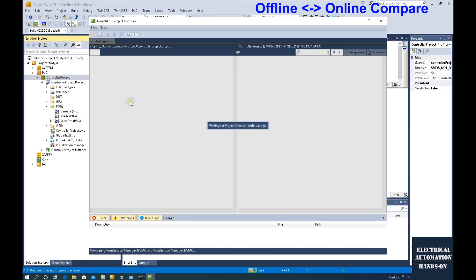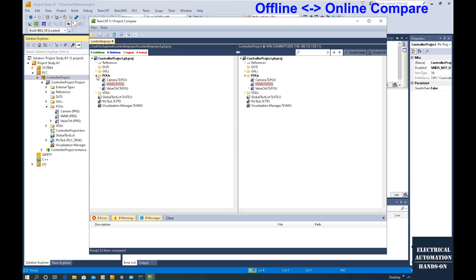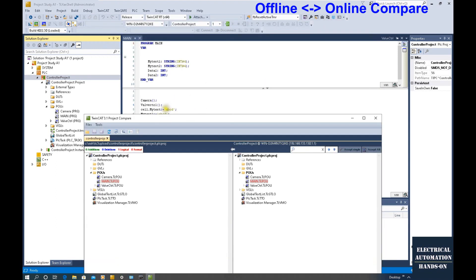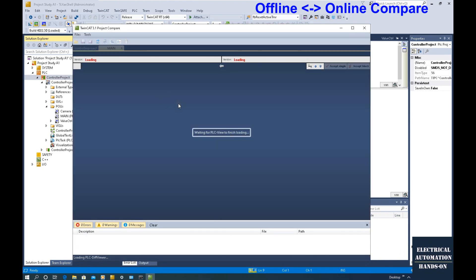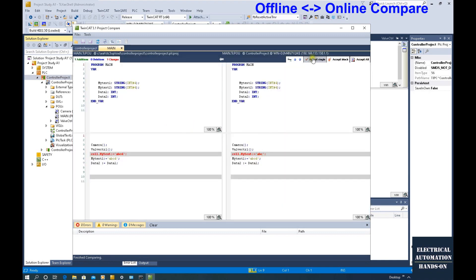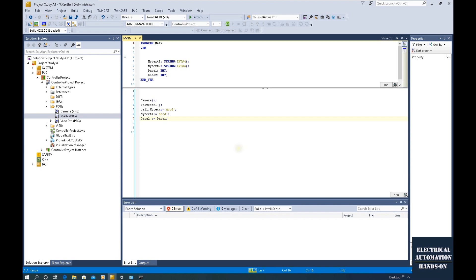The online PLC shows there the change. This way we can quickly find out where we changed — from offline comparing online. And another way we can compare offline with another offline project. For example, find the TwinCat config mode icon, right-click, go to Tools, and here is 'TwinCat Project Compare'. This is the source, and this is the destination — change the project. You can select and open another project. It will try to compare the source and destination project. Using these two buttons it will find the differences between the two projects one by one. It is very useful.